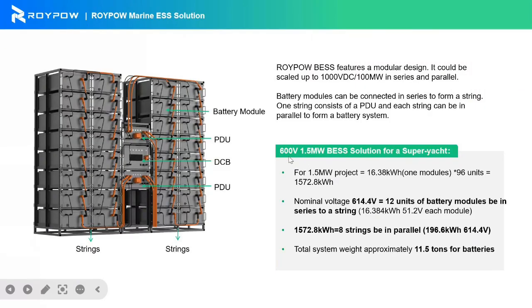So let's take an example of a BESS solution for super yachts. It's a 600 volt, 1.5 megawatt solution. We use our DNV approved 16 kilowatt-hour modules, 96 units, to reach 1.5 megawatts. We use 12 battery modules in series to form a string, and 8 strings in parallel. The total battery system weighs about 11.5 tons. We can also provide customers with the cables and racks, and our solutions can be customized based on the customer's different needs.